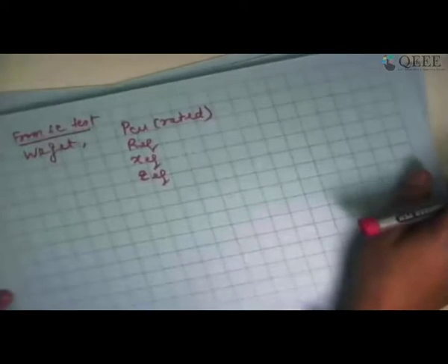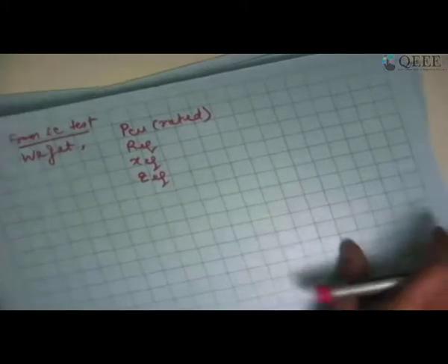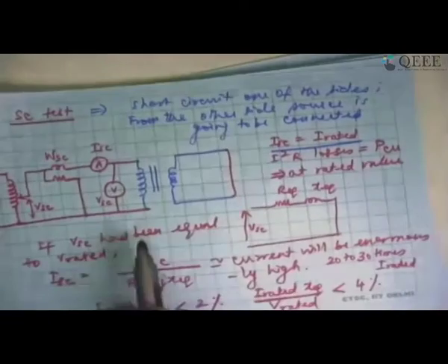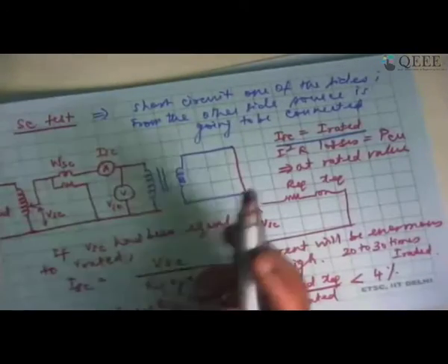So now that we have got all the data, we can draw the overall equivalent circuit again. Just to come back to short circuit test, from which side it is conducted. Short circuit is normally conducted only from the high voltage side rather than the low voltage side. What you are passing is rated current.